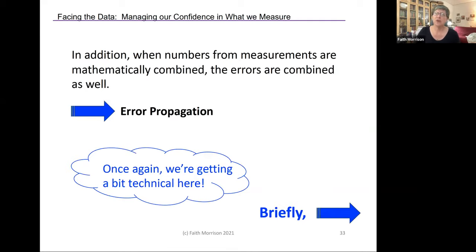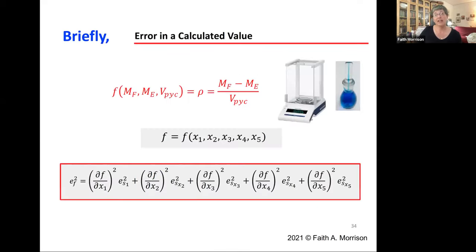And I would really like to drive a lot of practitioners back to the manual, which you can now Google up and get very easily to see what the manufacturer rates the instrument as being capable of. Because it may be that that's limiting the quality of your work. So I just one more quick thing. I want to show you, and that is how to combine errors and I'm not going to do it in detail, but that's the other thing that happens is that first of all, there are three types of errors. Even if you find three types of errors of the types I've indicated and you need to combine those.